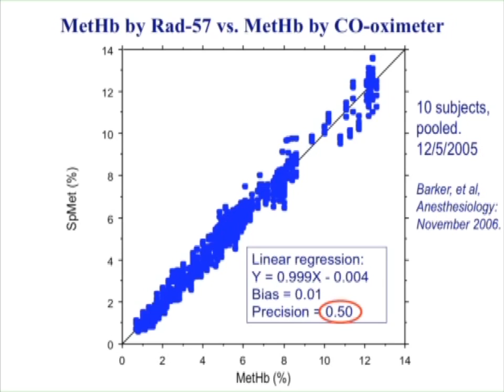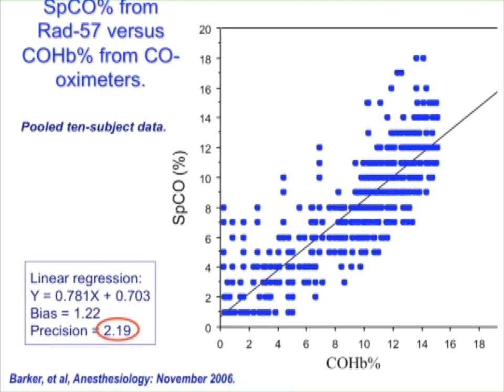Because look at the precision. Again, precision, standard deviation of the error or the random error, 2%. That's exactly the same as the precision of a conventional pulse oximeter for conventional SpO2 saturation. So that's the accuracy of the two. To summarize multi-wavelength, conventional pulse oximeters not only can't measure any of these dyshemoglobins, they can't even measure SpO2 in the presence of either of these dyshemoglobins, as I showed in my experiments.